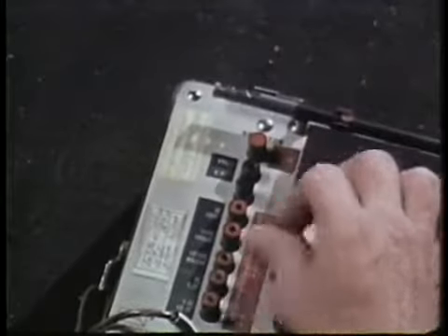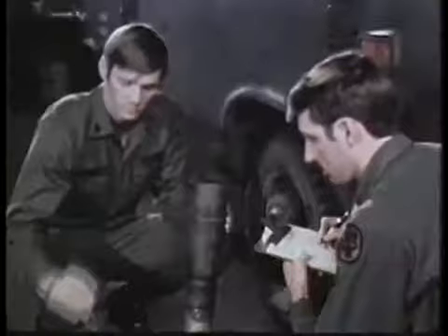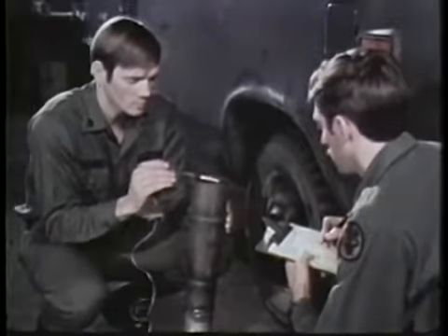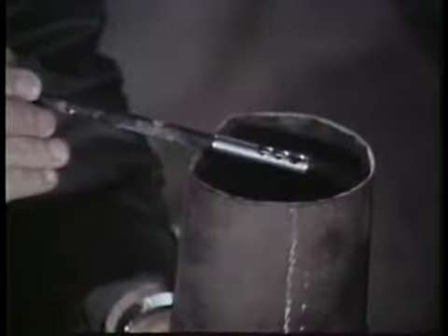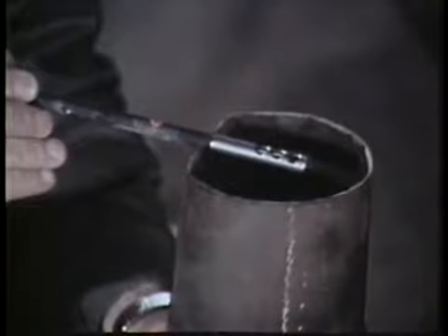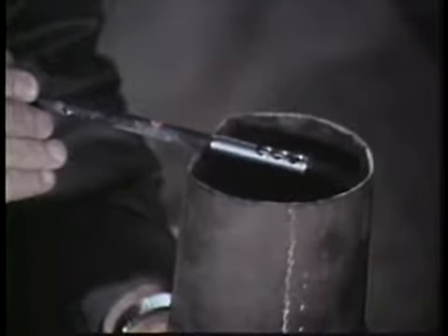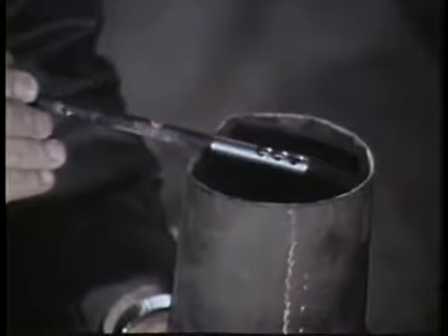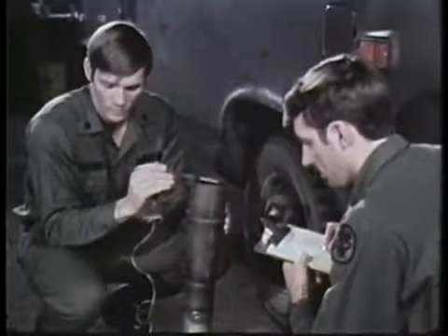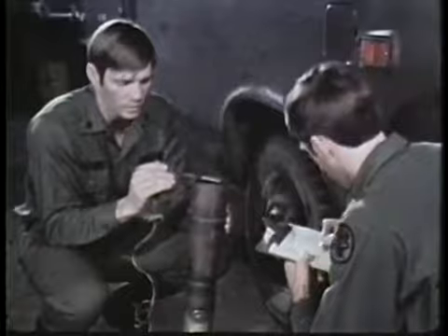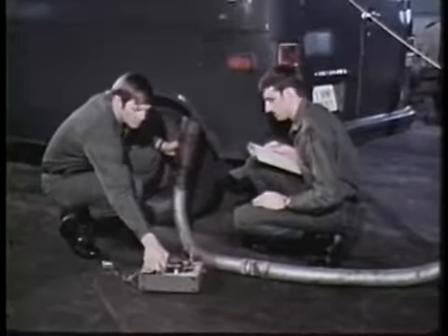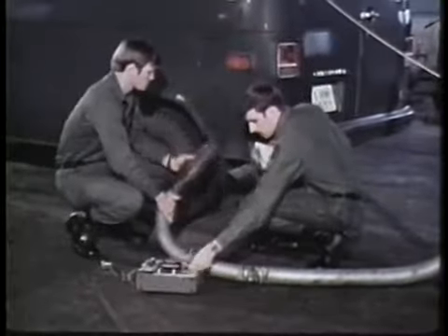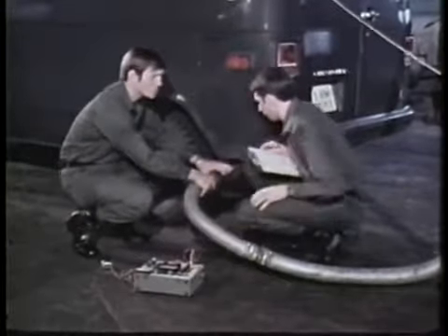Select velocity and the appropriate scale and take a centerline air velocity measurement. Turn the probe so the red dot is against the airstream, and with the probe 90 degrees to the airflow, hold the probe very still. You need to take air velocity readings at each outlet in the motor pool. This data you will later convert to volume of air moved.